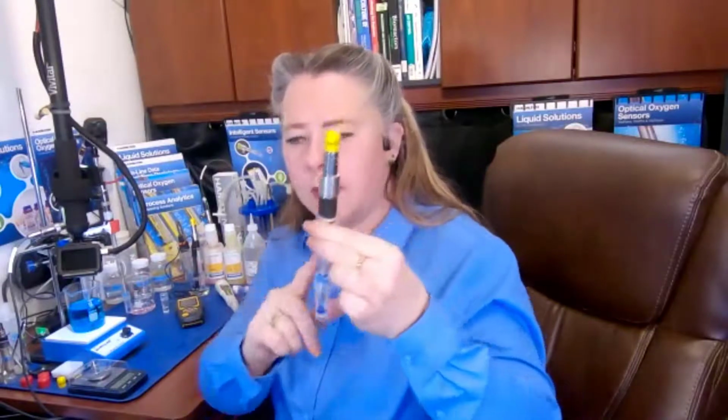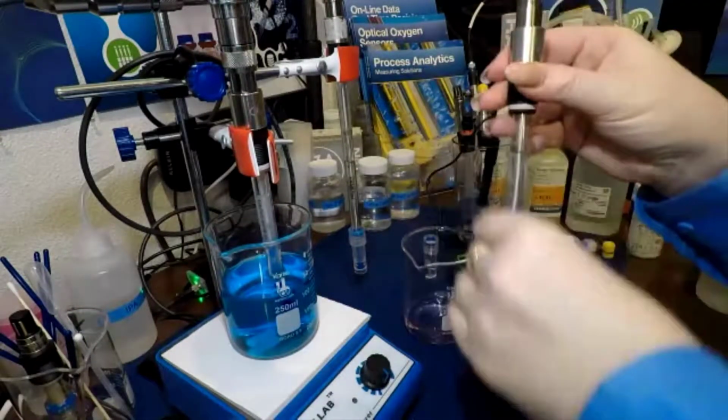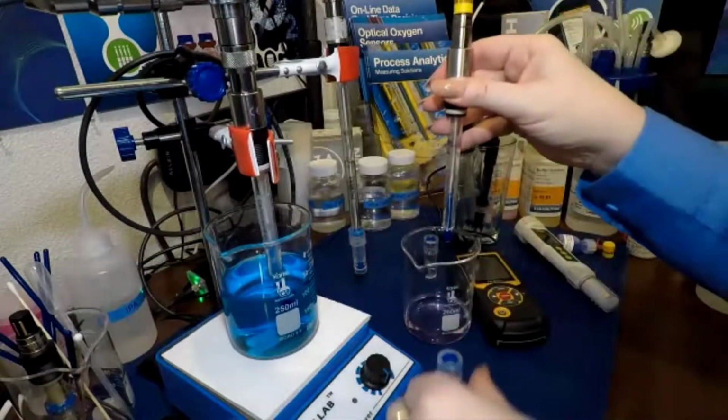When you're measuring in buffers, you should not just stick the probe in the solution and let it hang out sitting on the bottom, because that can deform that gel layer and cause some problems.